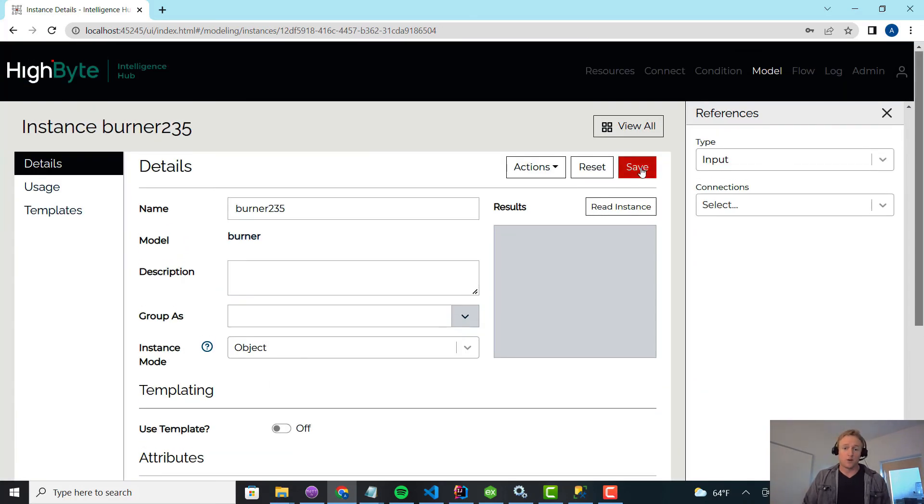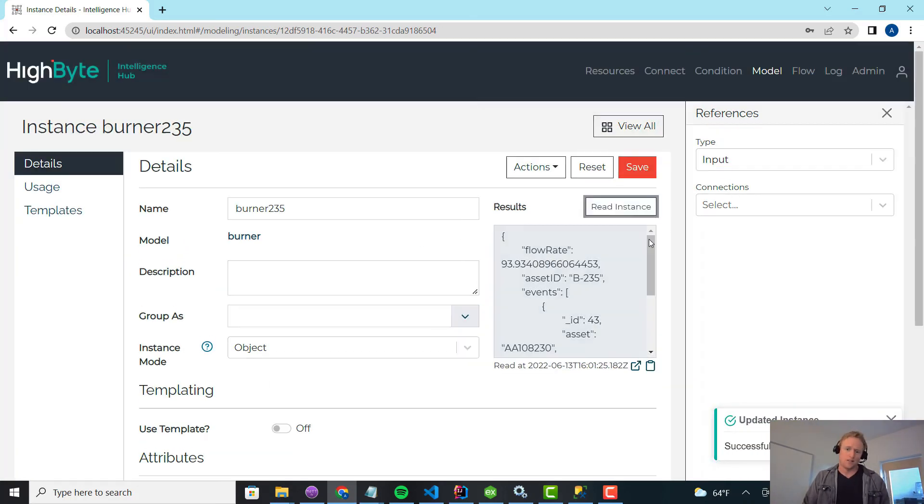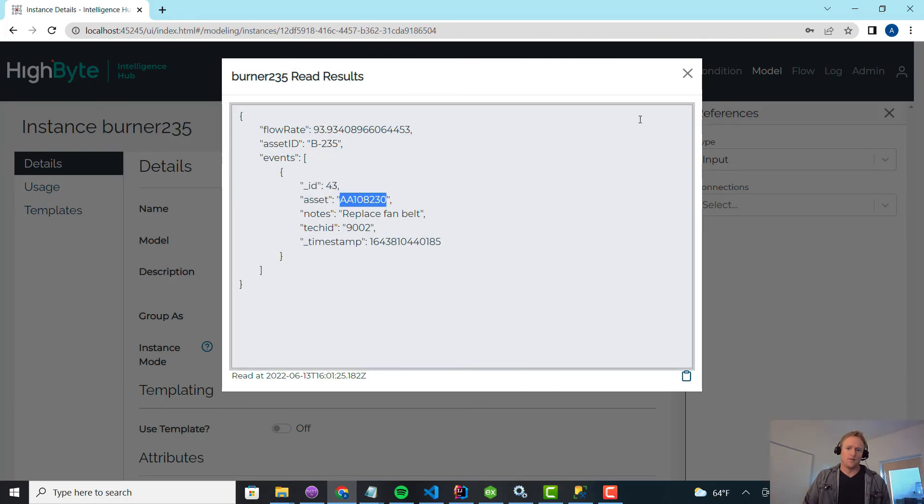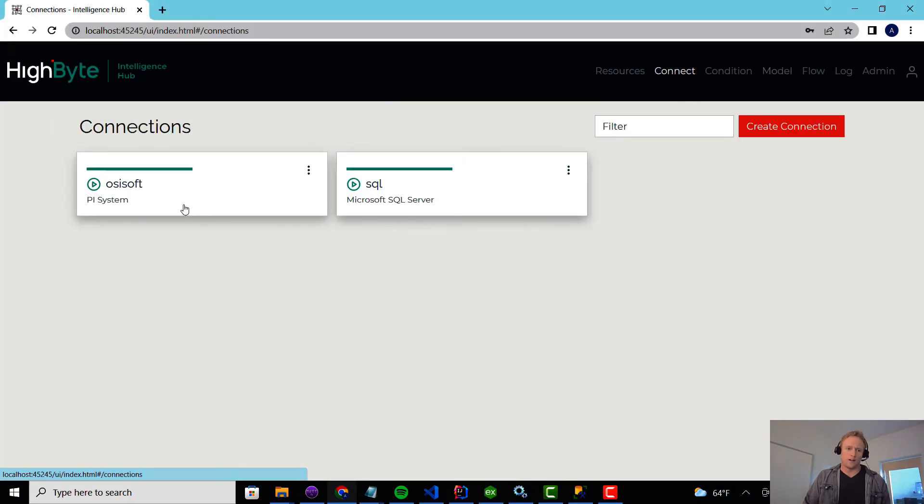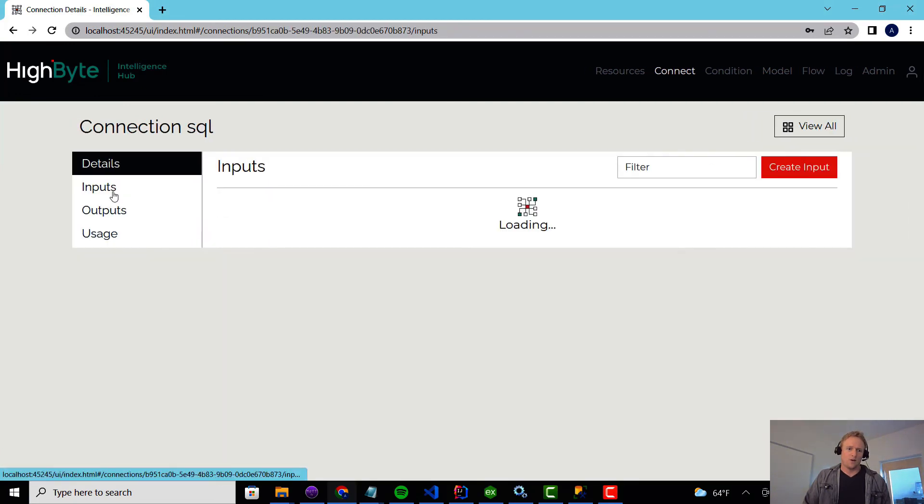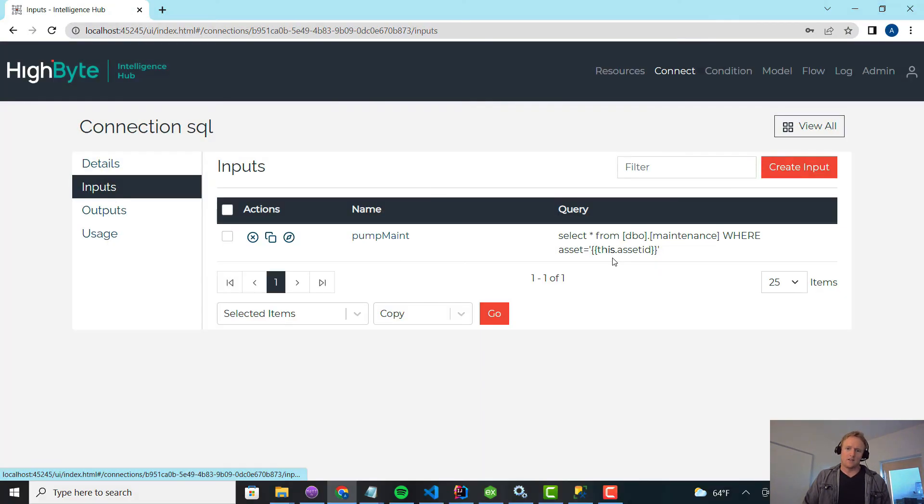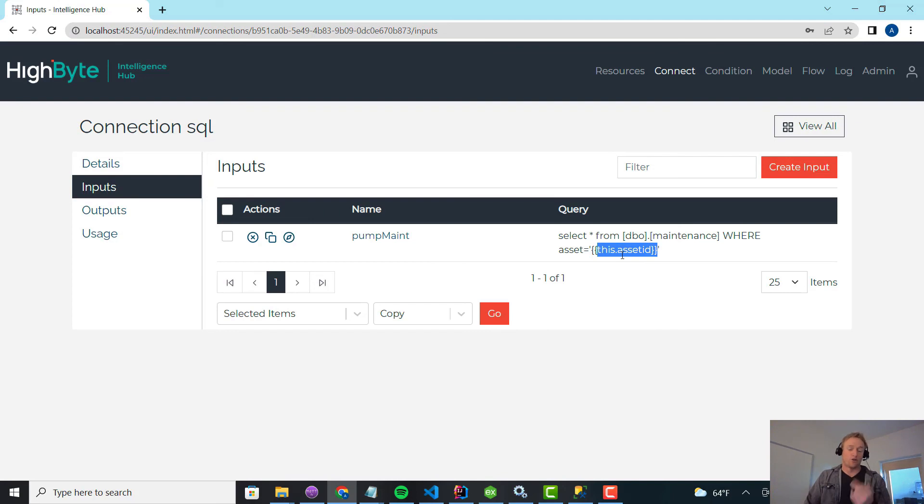So I'm controlling what this input is reading via the parameter. And I'm showing this over SQL, but it would work over MQTT, webhooks, any number of use cases. But now you can see I'm only getting the events from here. So rather than going to my SQL connection and having inputs for every asset ID, I have a single input that takes a parameter and I can control that at the instance layer. That's a very common use case. It really simplifies that in terms of limiting the configuration.